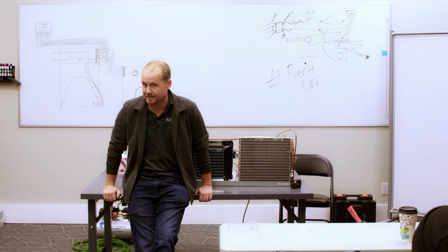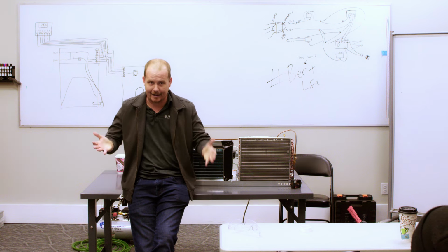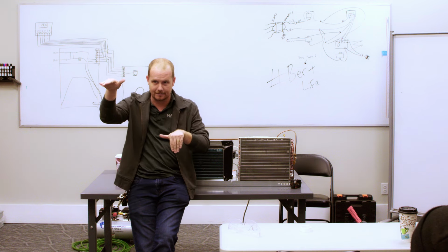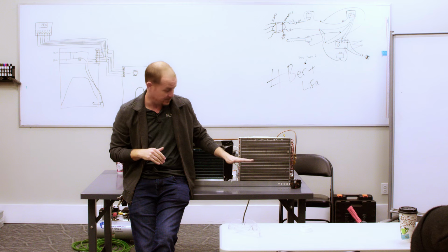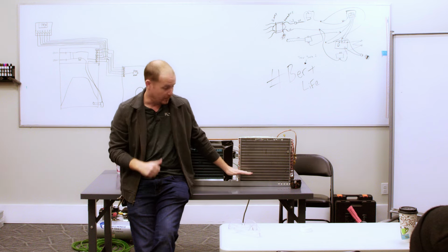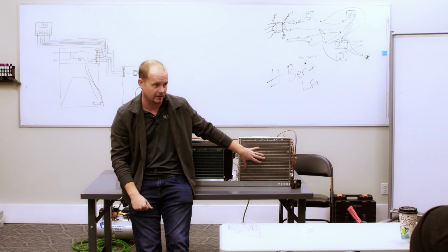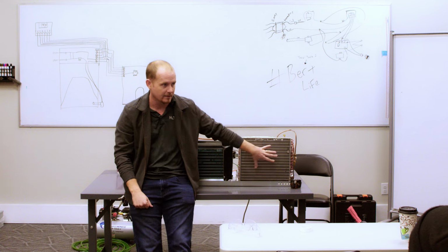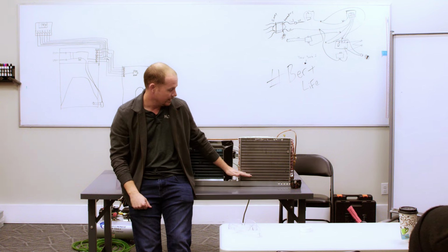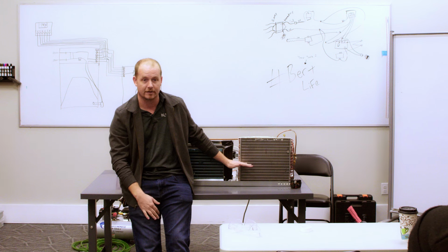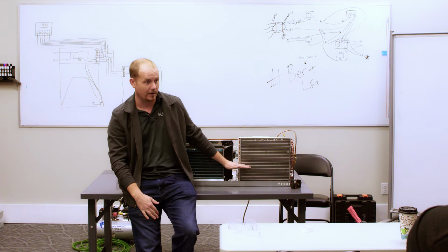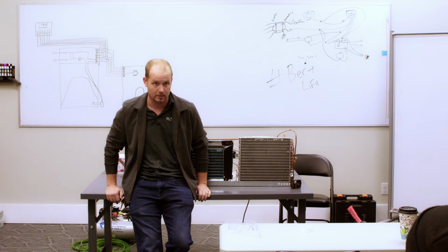I'm going to say that again because I think I made a couple quantum leaps there. What we're doing is we're stacking liquid in the condenser. We know that to a point we can stack liquid in the condenser and it doesn't really affect our condensing temperature because we have enough volume. But when we get to a point that we start stacking more in, you start to see your head pressure go up. That's not what we want.